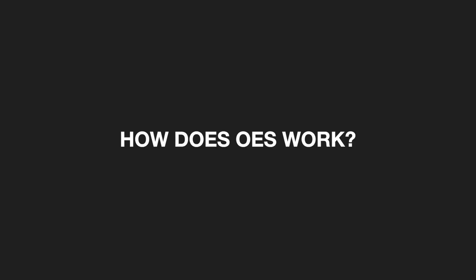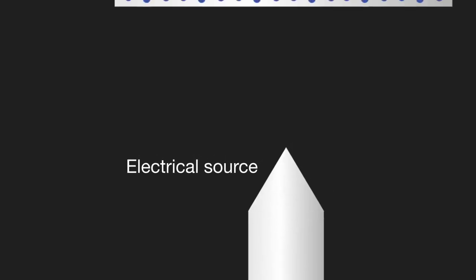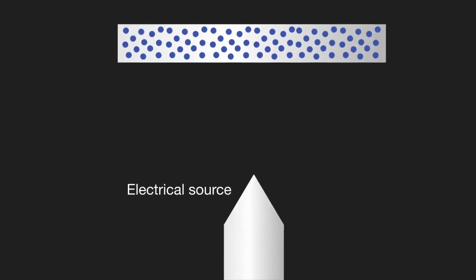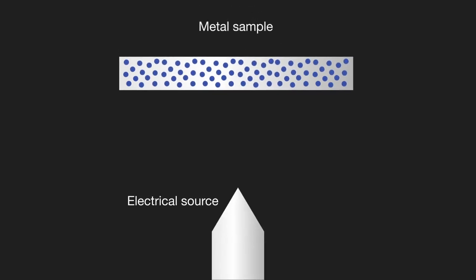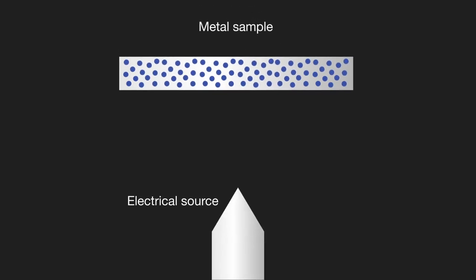So how does optical emission spectroscopy work? All OES analyzers contain three major components. The first is an electrical source to excite atoms within a metallic sample, so that they emit characteristic light or optical emission lines.